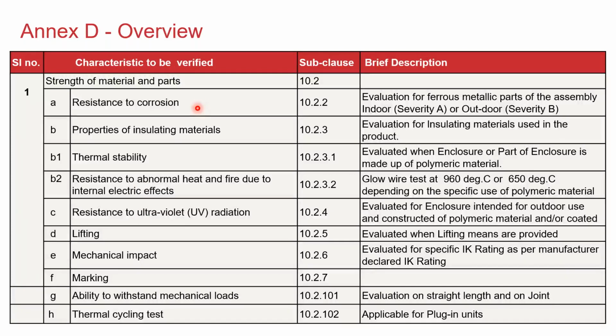If you look at resistance to corrosion, you will find that it is primarily intended for all the ferrous metallic parts. Most busways will have metallic enclosures, so you need to make sure those ferrous metallic parts don't corrode over time, and that is why this test has been introduced. Again, we have two classifications: one is indoor use, the other is outdoor. If it is for an indoor application, we perform a severity A test, and if it is for outdoor, we conduct severity B.